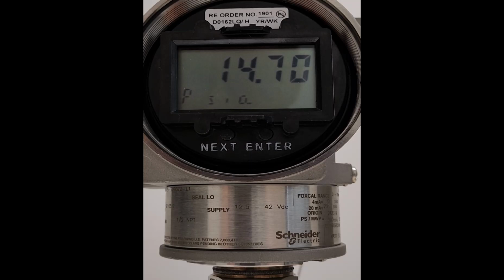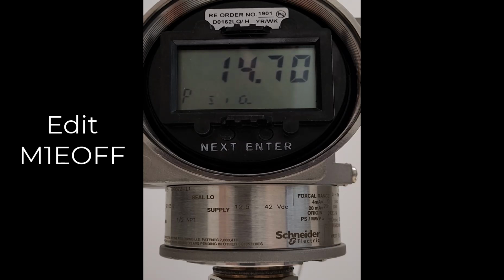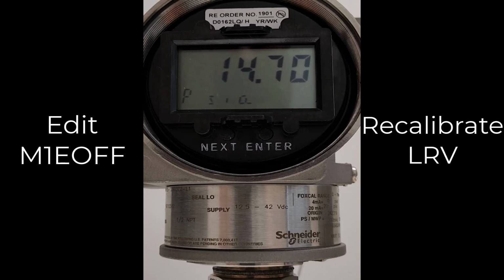In this demonstration, we're going to edit this transmitter to simulate gauge pressure. In other words, we want it to read 0 when it's vented to atmosphere. There are two methods for doing this. One is to edit the M1E off value, and method 2 would be to recalibrate the lower range value with the device vented to atmosphere.